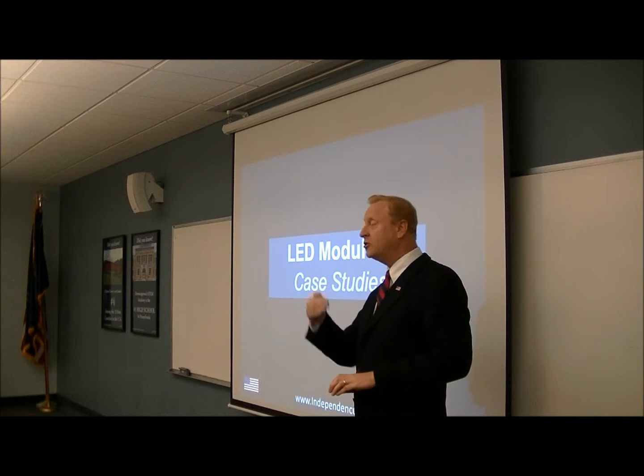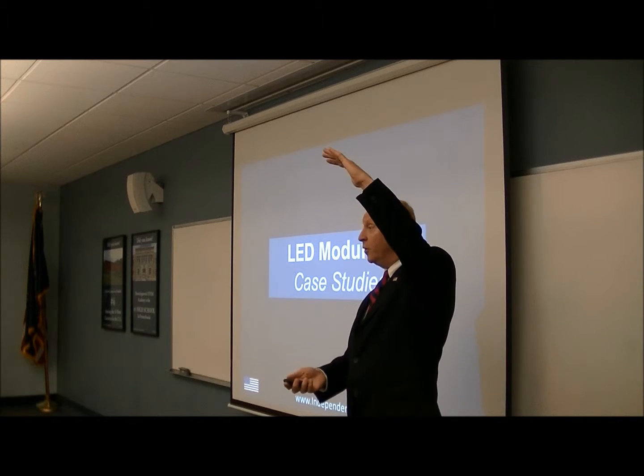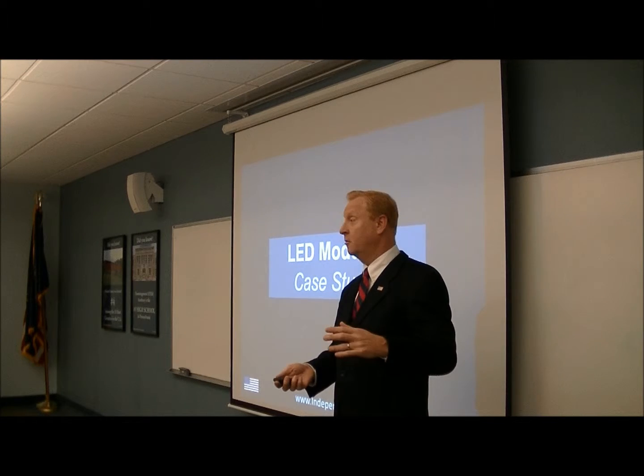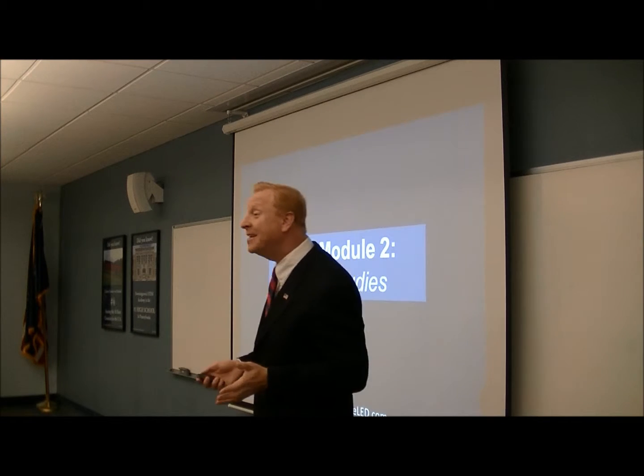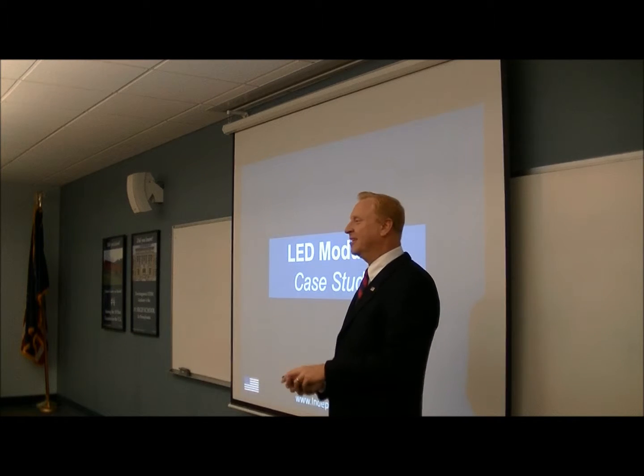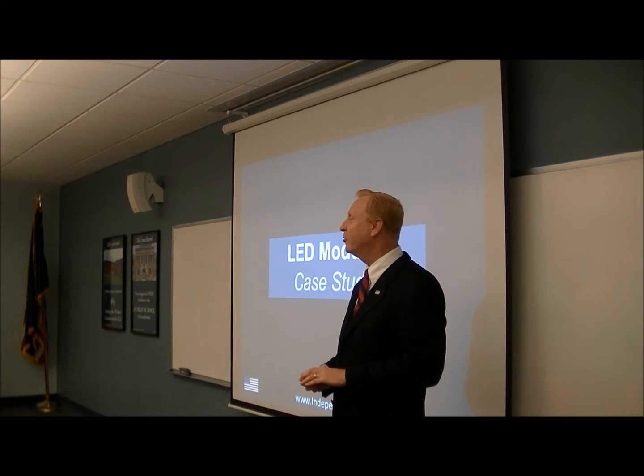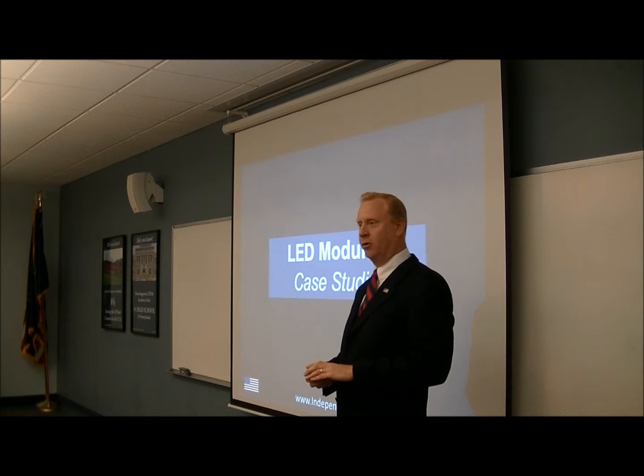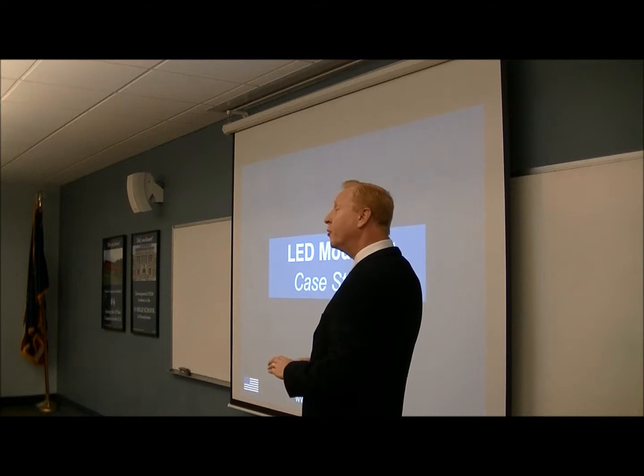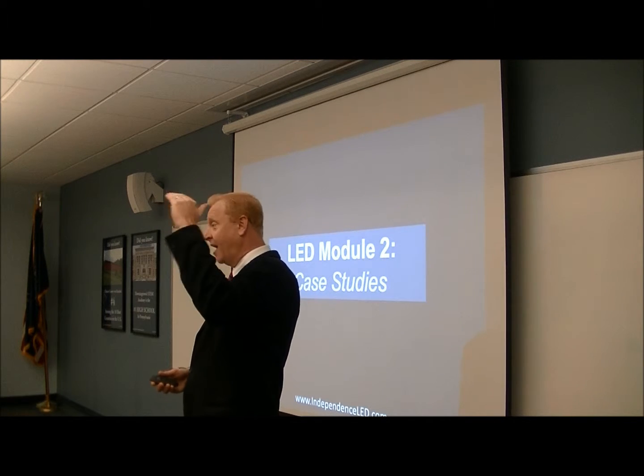70% of launch light is the death of an LED. Still got 70%. So when you've lost 30, it is deemed dead. Unlike fluorescent, which is literally dark. So what's going to be really interesting in 20 years is who just leaves the lights going. Because with computers on our desks, we have individual light sources, and we've largely overlit the world for commercial applications, given work environments. So it'll be interesting to see if they really go for 30 years. Because remember, they're not dead. This is solid state lighting.